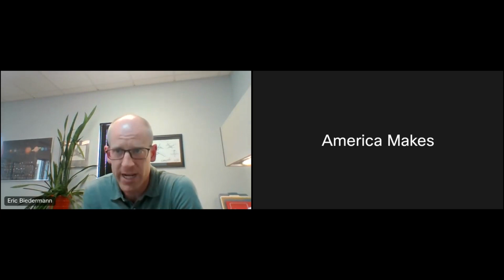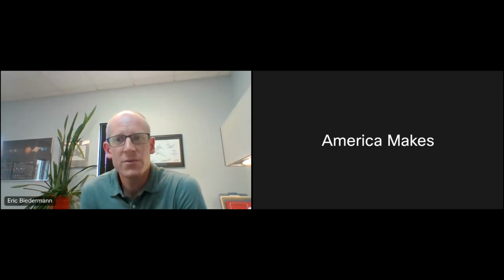Similarly, machining, the machine was another part of that question. Will machine performance affect results? Yeah, so we can detect variations in machine performance or machine to machine variation and help users quantify those effects. So if you have a machine that is performing off nominally, we can see that in the resonance data and detect it. So it's a great process control tool for both of those things.